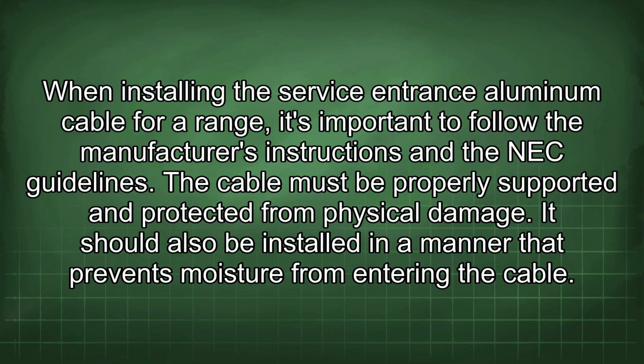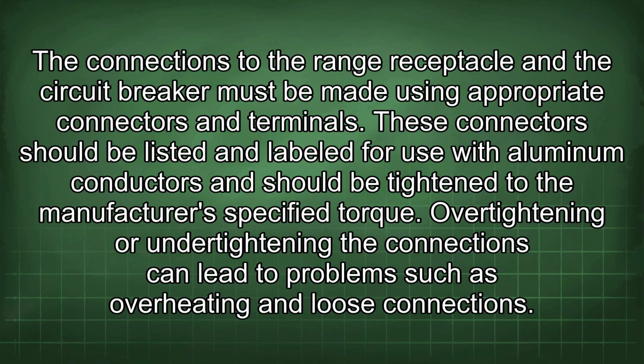It should also be installed in a manner that prevents moisture from entering the cable. The connections to the range receptacle and the circuit breaker must be made using appropriate connectors and terminals. These connectors should be listed and labeled for use with aluminum conductors and should be tightened to the manufacturer's specified torque. Over-tightening or under-tightening the connections can lead to problems such as overheating and loose connections.